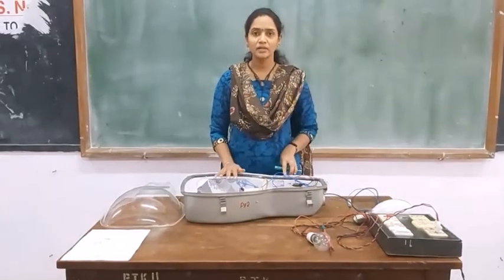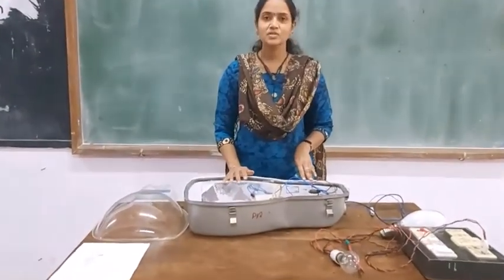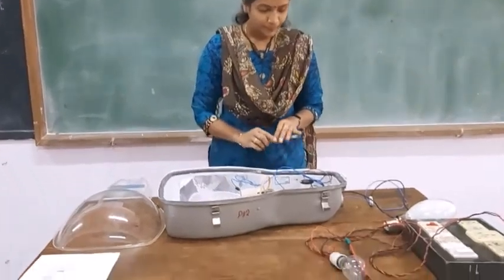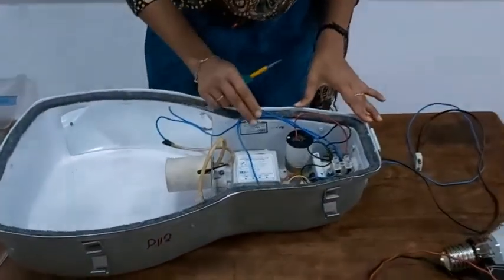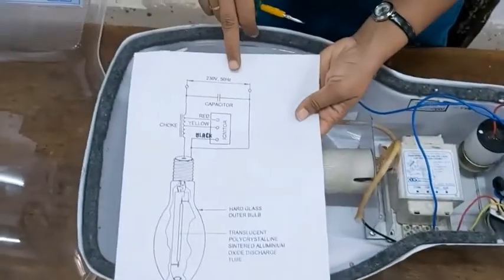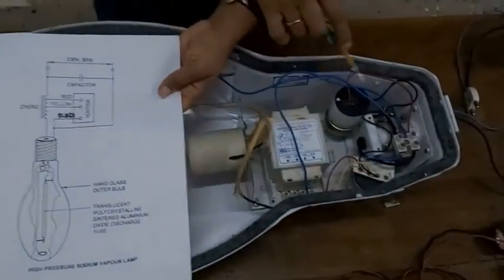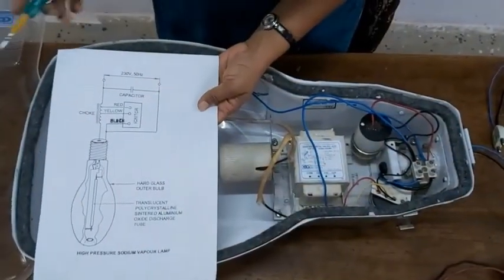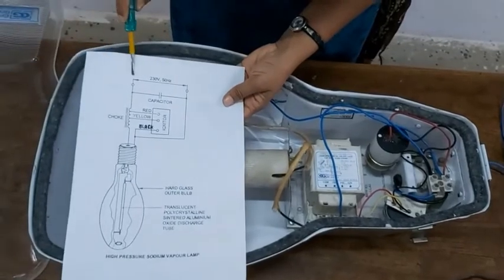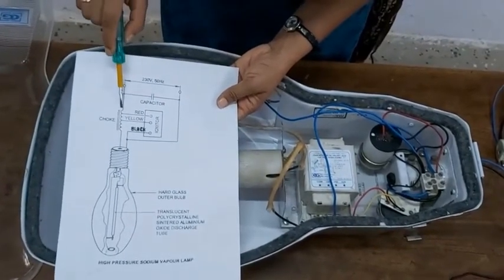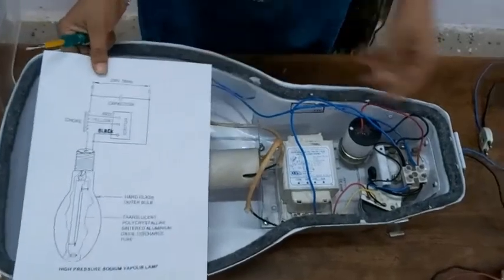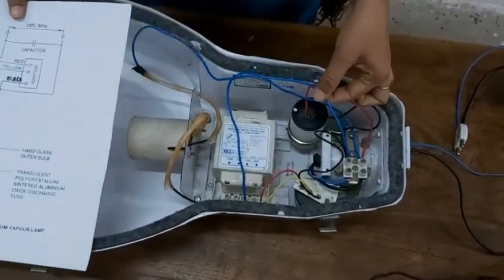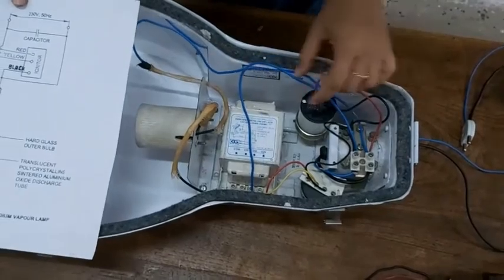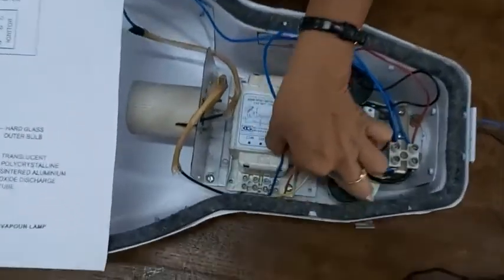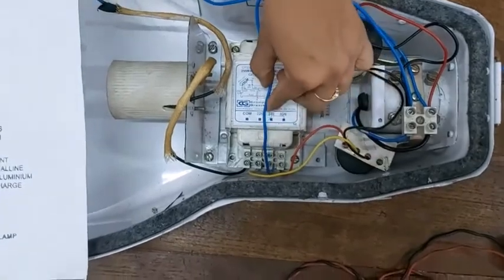Now I have reassembled all the parts of the high pressure sodium vapor lamp set. The connections are made as per the circuit diagram. This is the circuit diagram. Here I have done the connection as per this diagram. The phase wire of the supply is connected to the choke, that is, this blue wire. This blue wire is connected to 240 volts of this choke.